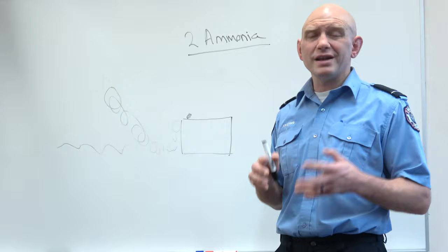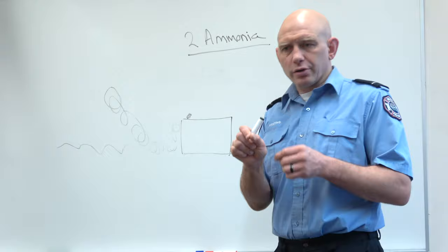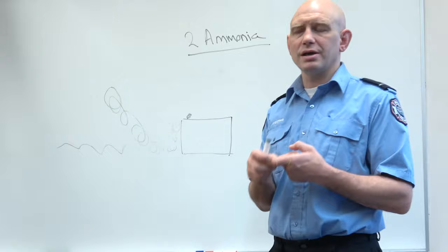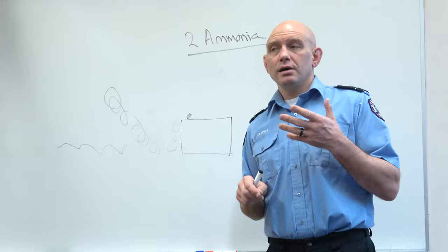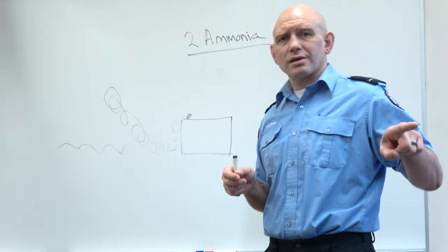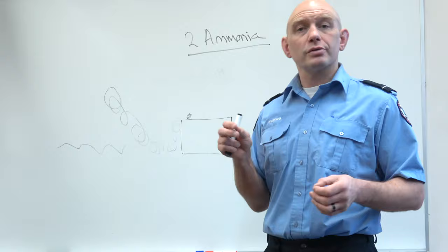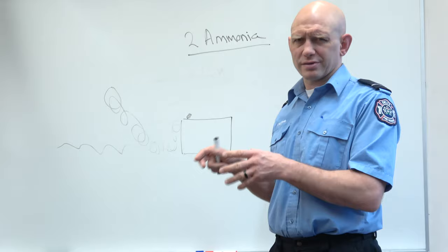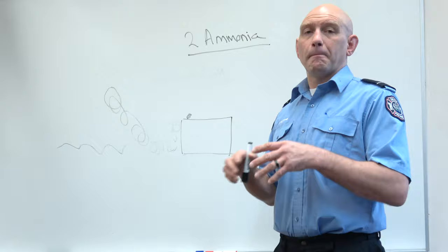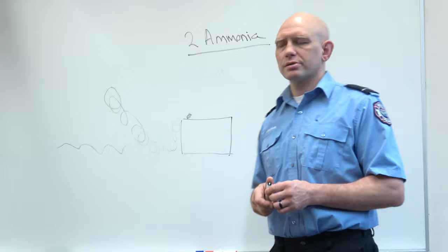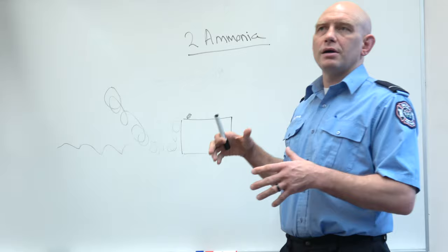Of course, it also means that on a foggy, foggy day or a rainy day, that ammonia is going to be hanging around at ground level a lot more. Say we had an ammonia release at the top of a building here at a refrigeration facility. Ammonia is lighter than air, but it doesn't go up right away. When it comes out, it's super cold. Super cold meaning it's condensed, meaning the vapors are going to go down first, then they're going to roll along the ground, and then eventually as they warm up, they're going to go up.